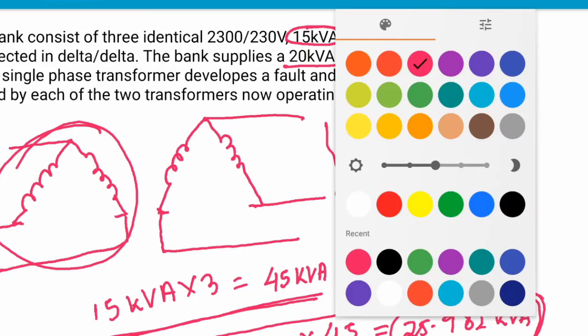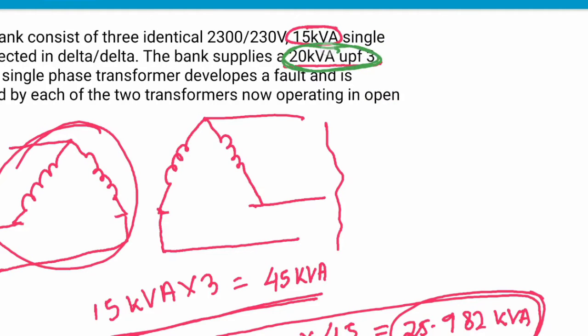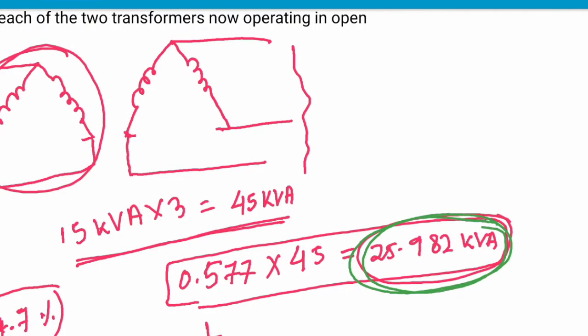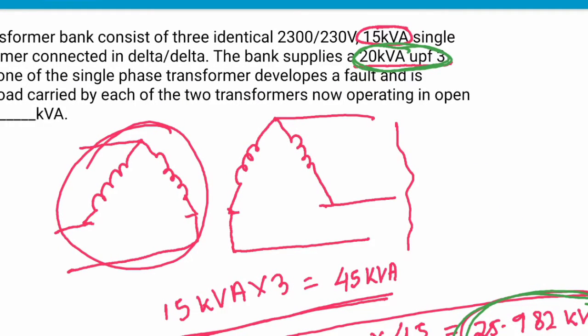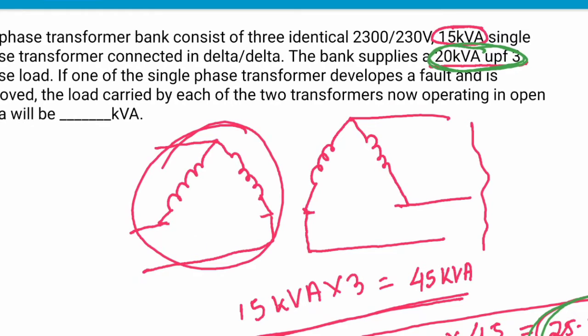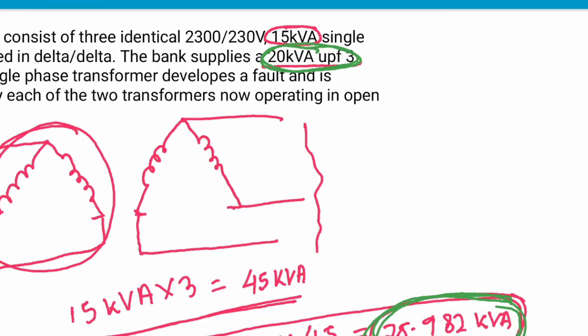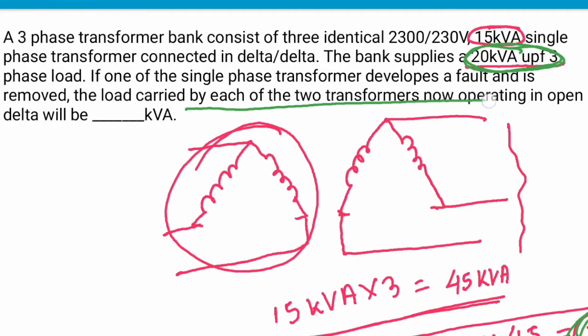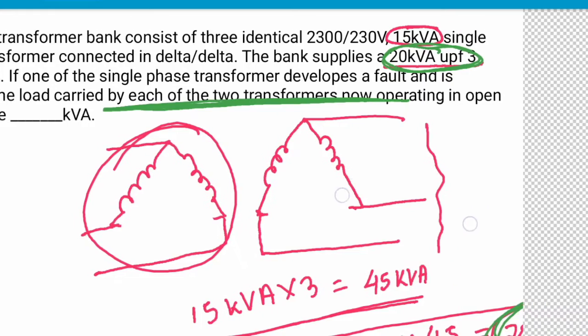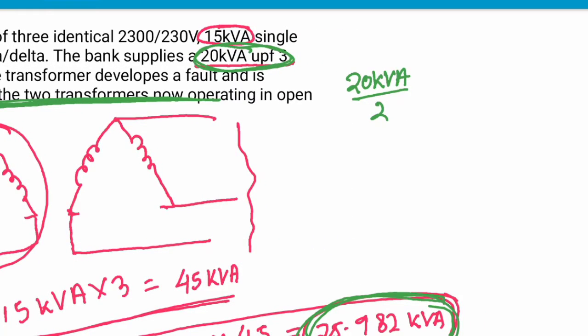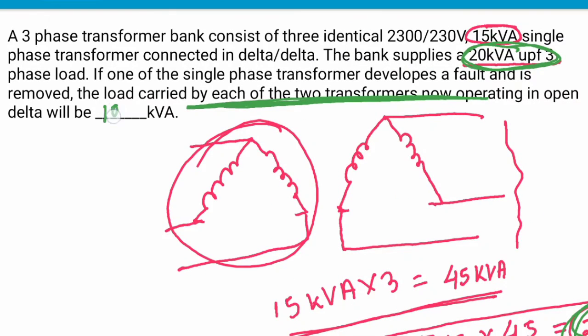Now this is the new rating, but in the question it is given that it is providing only 20 kVA, which is less than even the new rating. So nothing will happen, it will still provide 20 kVA in the new connection, and it can go on in the future because it is providing less than that 25 kVA. So the answer will be 20 kVA by 2, because it is asking the load carried by each of the two transformers. The total load is 20 kVA, and the load carried by each transformer will be 10 kVA. So the answer will be 10 kVA, no doubt.